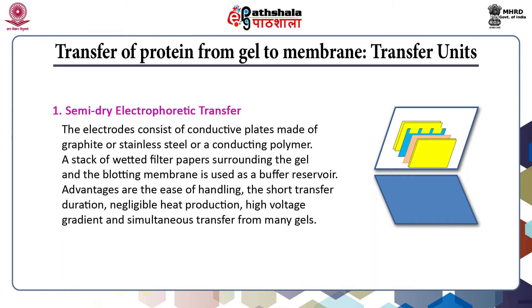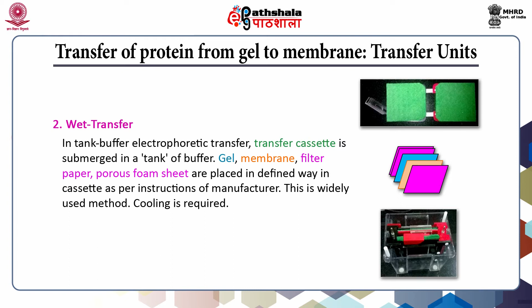Because of a short electrode distance, voltage applied is most often 10 to 20 volts only. On the other hand, because of the large cross-sectional area, the current passing through the transfer sandwich is fairly high, in the range of 0.1 to 1 ampere. In wet transfer unit, the transfer cassette is submerged in a tank of buffer. Gel, membrane, filter paper, and porous foam sheet are placed in a defined way in the cassette as per the instructions of the manufacturer. This is a widely used method.